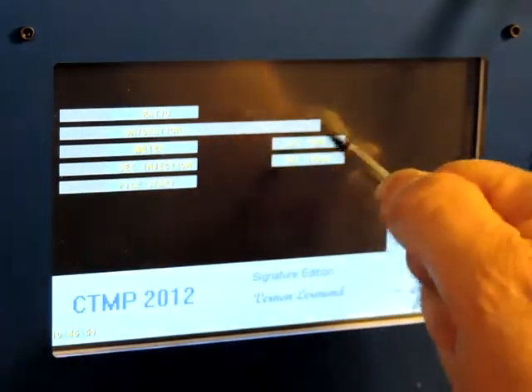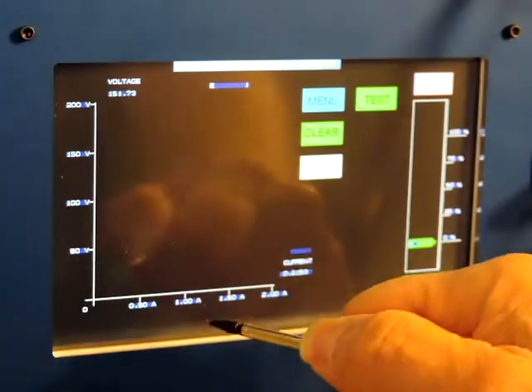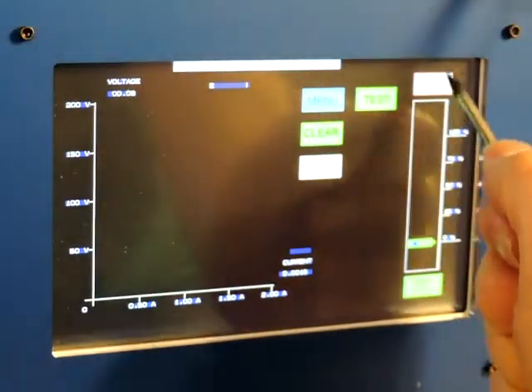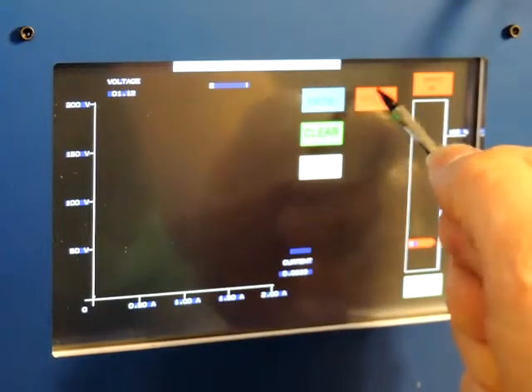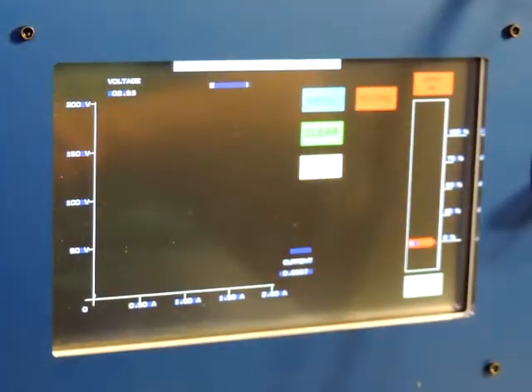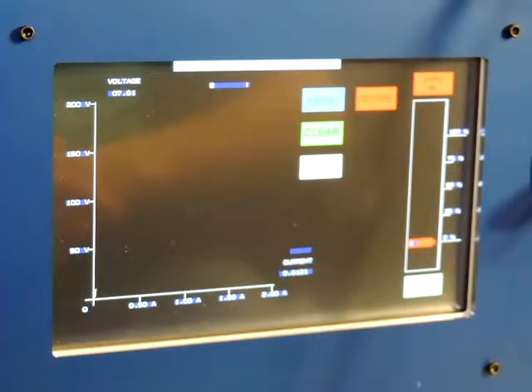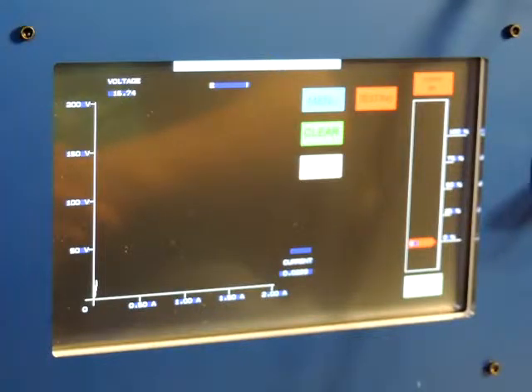Next, go to a saturation test. I know this CT will saturate on the 200-volt scale, so I'll select the 200-volt scale. Turn the output on and press the Test button — it will say 'Testing.' Then all you have to do is wait while the unit performs the test. It's completely automatic, including saving the data to the drive.